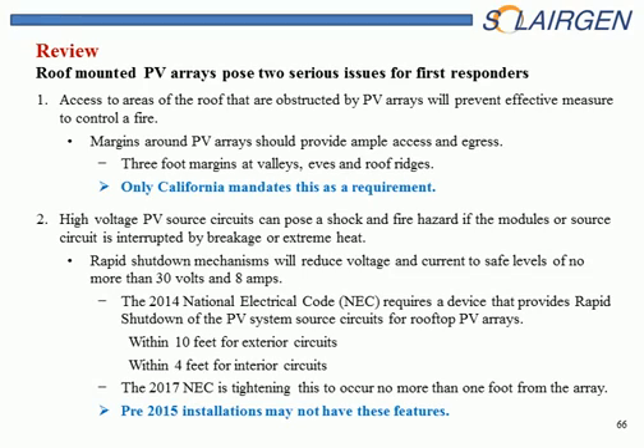High voltage, especially high DC voltage, can create quite a hazard for starting a fire, a secondary fire, or a shock hazard. If we have rapid shutdown mechanisms, which would be PV optimized SolarEdge inverters or microinverters, then we really don't have an issue. If it's prior to that, let's say 2012 and earlier basically, then we may have a high voltage issue. So we have to look for that conduit that feeds from the PV array down to where the inverter is.